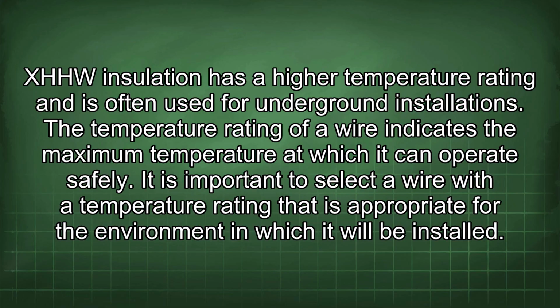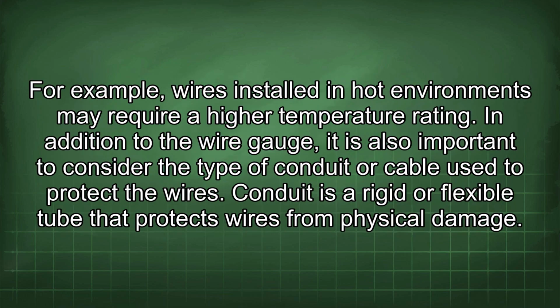The temperature rating of a wire indicates the maximum temperature at which it can operate safely. It is important to select a wire with a temperature rating that is appropriate for the environment in which it will be installed. For example, wires installed in hot environments may require a higher temperature rating.